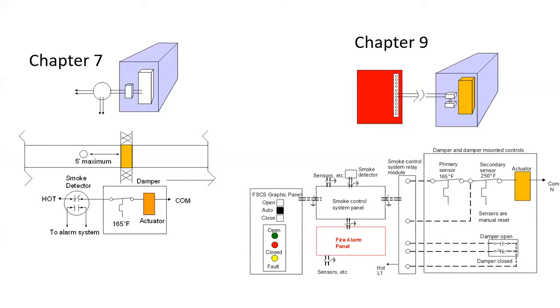So right there, shown on the right side, is a reopenable damper. It can be overridden from the firefighter's smoke control panel. Position indication is required so that the incident commander during any event can see whether dampers are open and closed, and they can get messages from any firefighters on the floor whether they need to exhaust smoke or to pressurize the space. So they're a lot more complicated. A lot more fun.